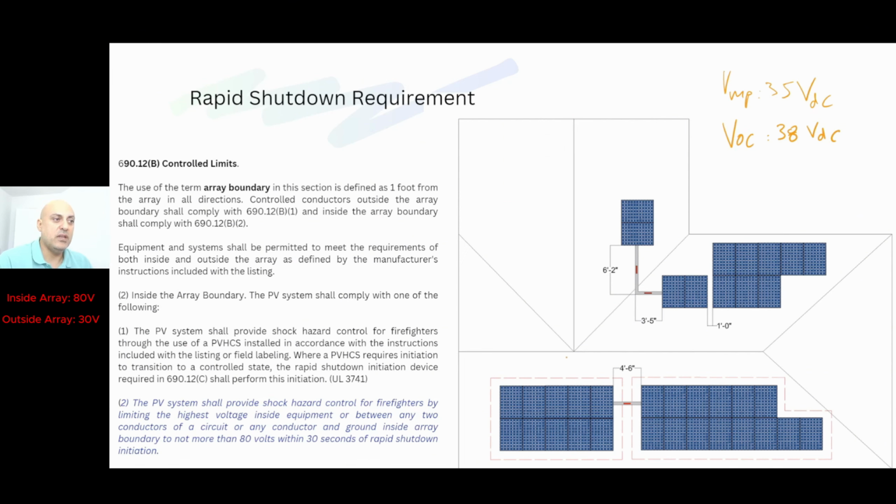So let's say that I have these sections here, right? And I'm deciding to install a rapid shutdown that allows me to have 2 panels per each one of them, right? So if I install my rapid shutdown here, I install this panel here and this panel here, I'm not connecting them in series. Then I have another rapid shutdown here, and I do the same with these ones. But now, okay, what's going to happen here?